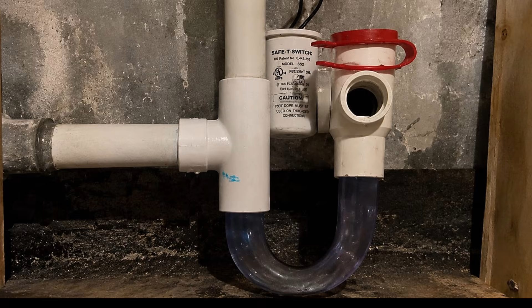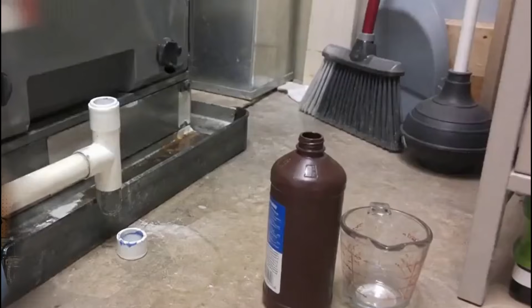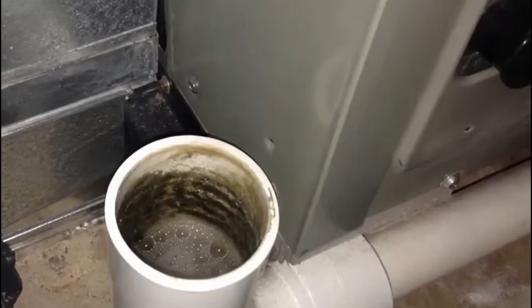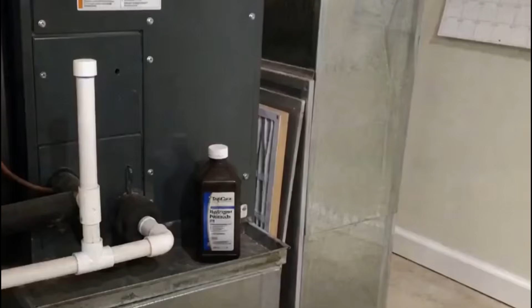The pipe was dirty. Find the T-shaped fitting with a cap on that pipe near your indoor unit. Pull the cap and pour in a cup of your fresh 3%. You'll hear it fizz as it eats the slime and lifts it off the wall. 10 minutes, then flush with warm water. Do that once a month through cooling season, and that shutdown never comes.